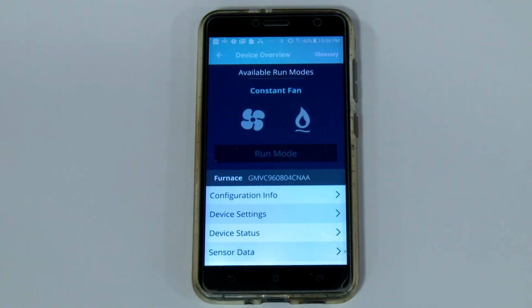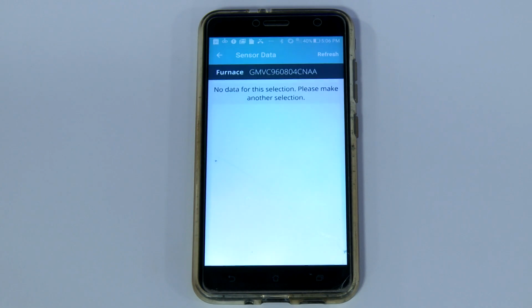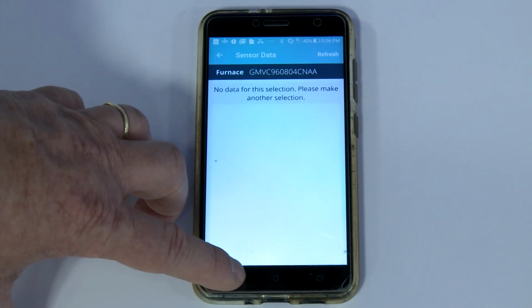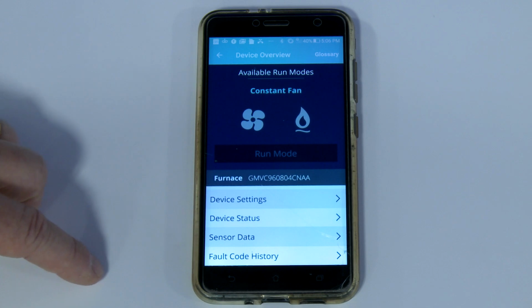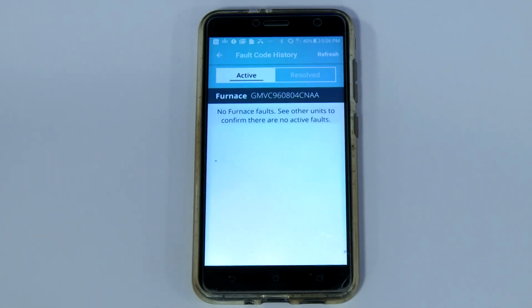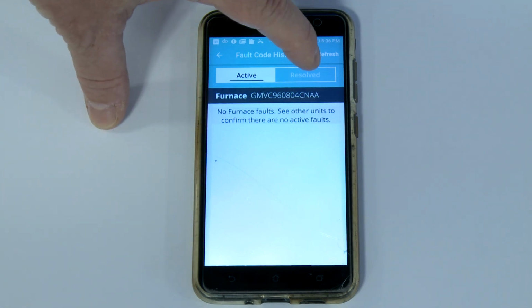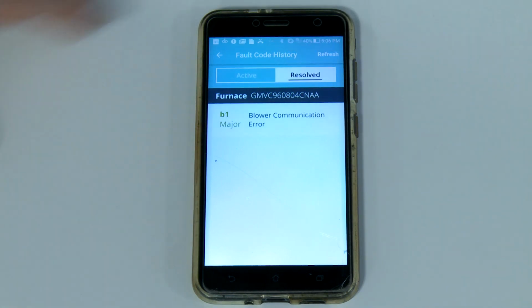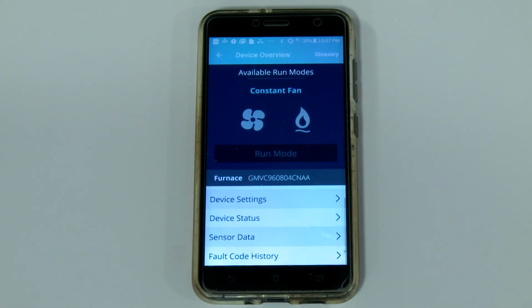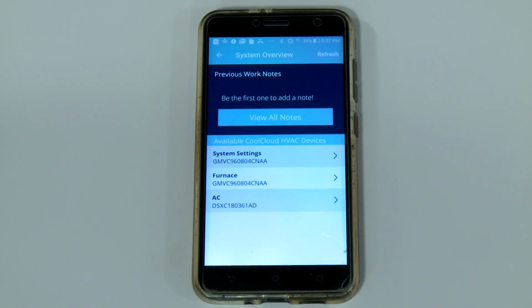The Sensor Data menu shows input from sensor devices connected to the indoor and control board. In this case, we have nothing connected to the indoor board, so nothing is visible. Let's move to View Fault Code History. If any active fault codes exist, they'll be listed in this menu. It's possible to review the resolved fault codes too. In this example, there's a blower communication error which was likely initiated during one of the test runs of this piece of equipment.